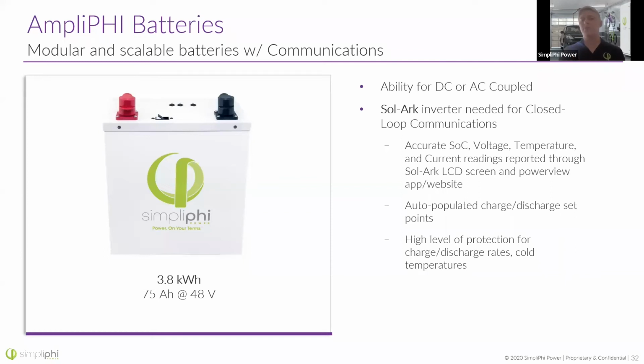Now this is super helpful for us in the tech support department when there's an issue and we're trying to troubleshoot. I'd say we solve these 10 times faster when there's accurate monitoring on the system. In addition, it's going to help you out a little bit as the installer by automatically programming certain settings like charge and discharge rates. And it's also going to add another level of protection for cold temperatures and small systems.